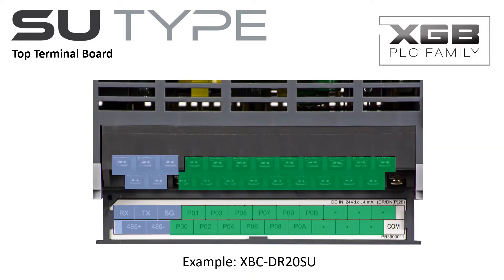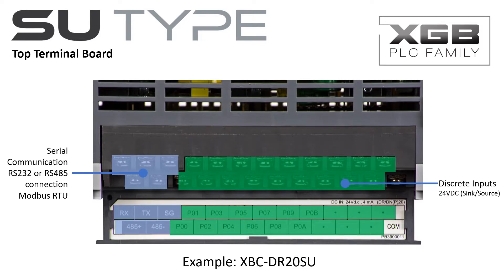The top terminal board provides connectivity to the two serial communications ports. One RS-232 port and one RS-485 port are available. Both ports can be configured for Modbus RTU, LS-dedicated or user-defined protocols. The PLC's discrete inputs are also on the top terminal board. The inputs are 24V DC and can be wired as sink or source inputs.